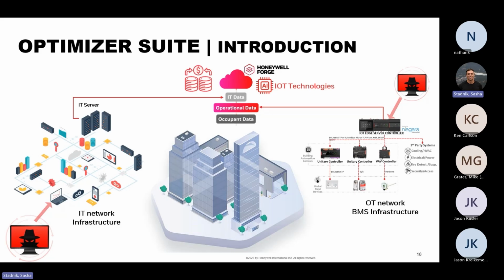When it gets fully isolated, like the advanced controller, then I can block access from here to there and from there to the BMS. This is so important because in the terrorist case I was talking about, if the terrorists want to access the server just to access the BMS to start controlling temperature and humidity, if that thing is switched, they can do that. But if this thing is completely isolated, there's no way.